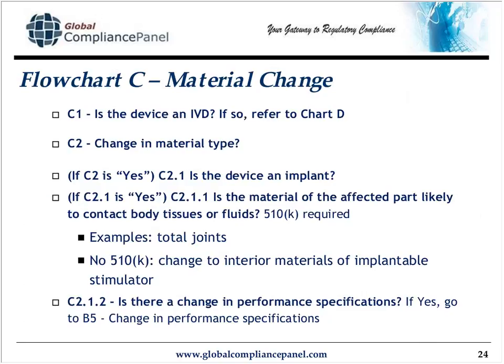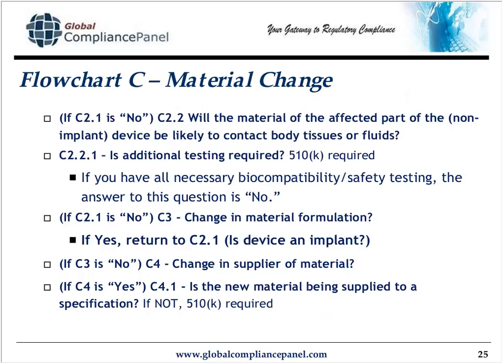C2.2.1 says, based on ISO 10993-1, which is the biocompatibility standard, is additional testing required? And what's important here on the second bullet point, additional testing required, 510K required, under 2.2.1, is the word additional. If you have already performed biocompatibility testing, then the answer to this question is no, additional testing is not required.